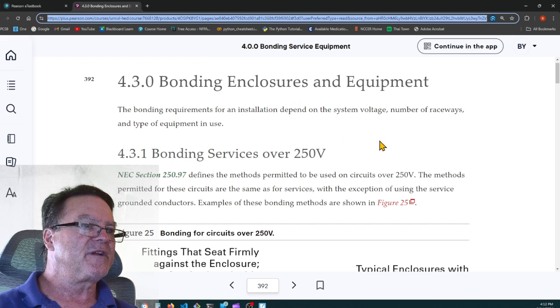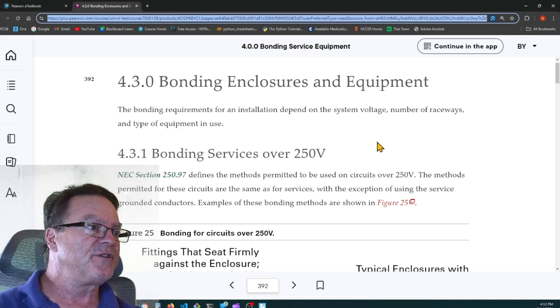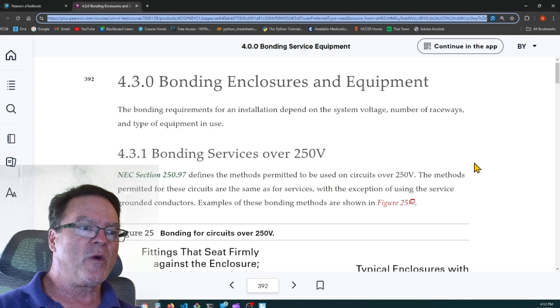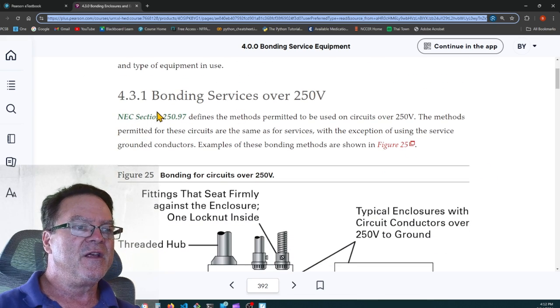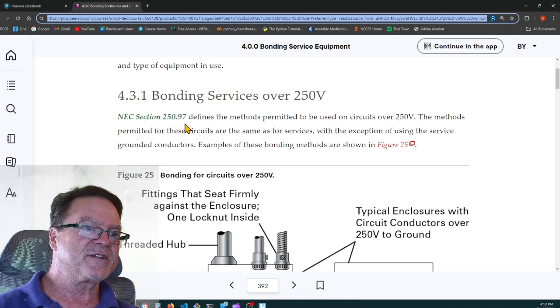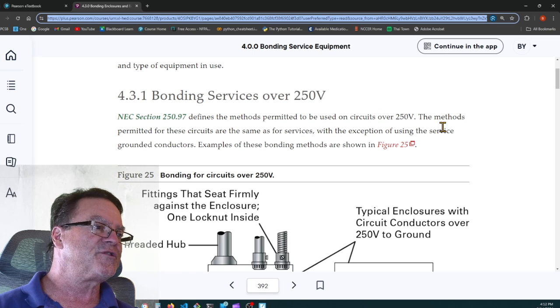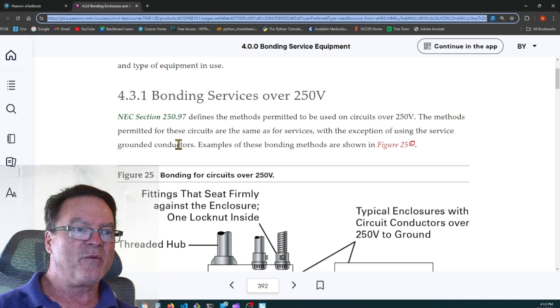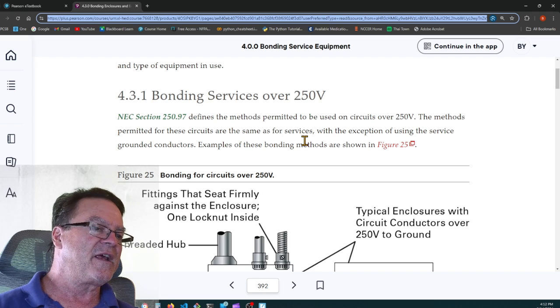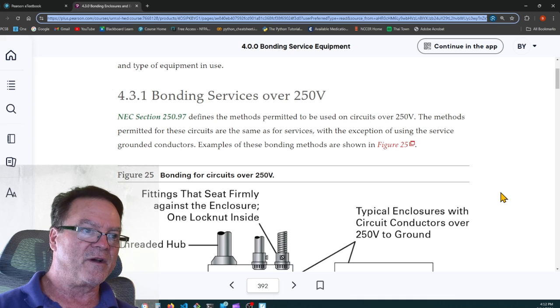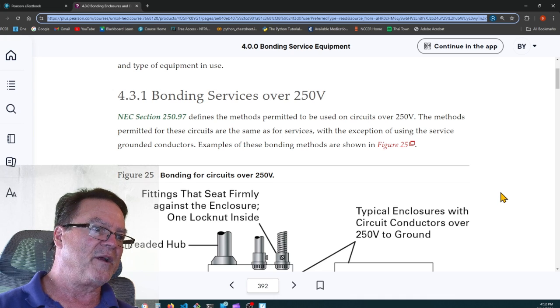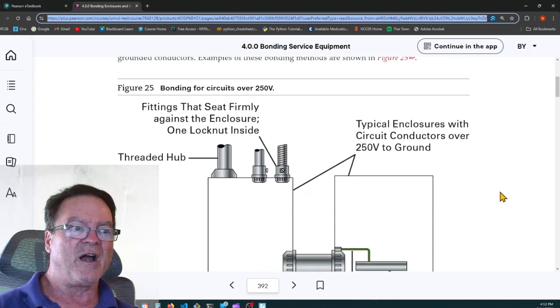4.3.0, bonding enclosures and equipment. The bonding requirements for an installation depend on the system voltage, the number of raceways, and the type of equipment in use. So, bonding services over 250 volts. NEC section 250.97 defines the method permitted to be used on circuits over 250 volts. The methods permitted for these circuits are the same as for services, with the exception of using the service grounded conductors. Examples of these bonding methods are shown in figure 25.